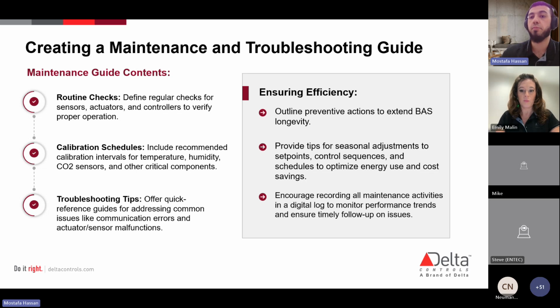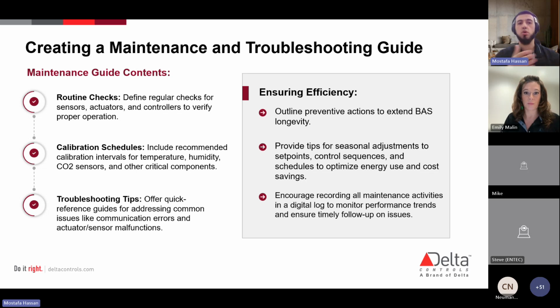This is about even if you're making a new system, putting in a new building automation system, or retrofitting, it doesn't matter. There's still going to be a sequence that as a consultant you're designing, and you're going to create a maintenance and troubleshooting guide for the equipment going into the field, whether you're retrofitting or creating a whole new building automation system. I don't think it matters whether you're converting from another system. In all scenarios, you should have a maintenance and troubleshooting guide, because someone's going to be sitting in front of that operating workstation, and you want to give them tips on how to manage that system. Whether the vendor or controllers you're using in that space tie into a master head end that uses a different vendor's controllers, you still want a maintenance and troubleshooting guide. That will usually also come from the manufacturer of the retrofitted control space.